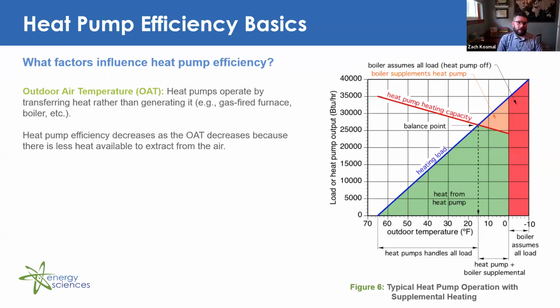So this is a representative example of how a heat pump may interact with other heating and/or cooling systems within a facility, whether that be a boiler, a furnace, a chiller, cooling tower, etc. It should also be noted that the turnover temperature, or the outside air temperature at which the heat pump cannot handle the heating load on its own, will depend on the system's design, okay? It's not always going to be 15 degrees Fahrenheit or 0 degrees Fahrenheit. It'll depend on that design, and it may vary depending on the specific application and heat pump equipment type, okay?